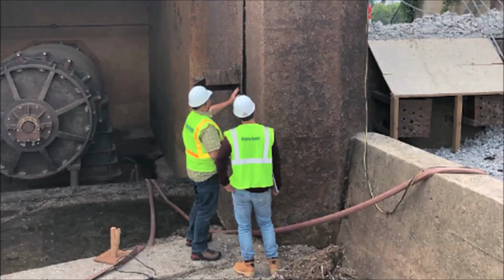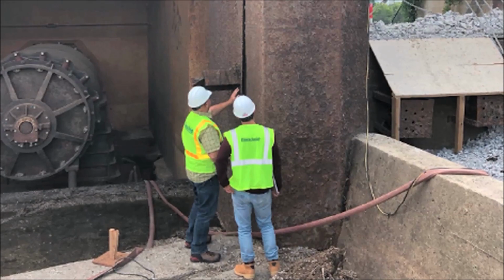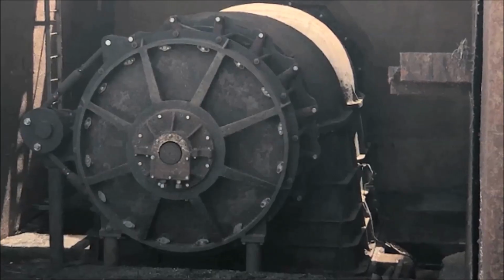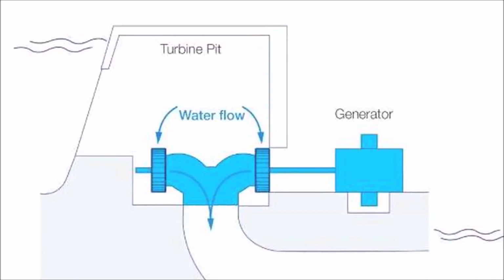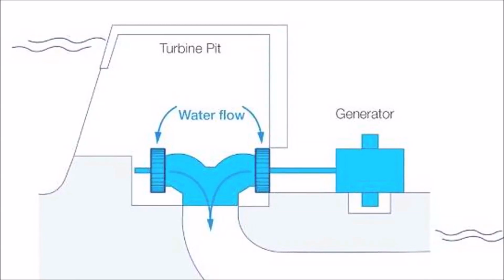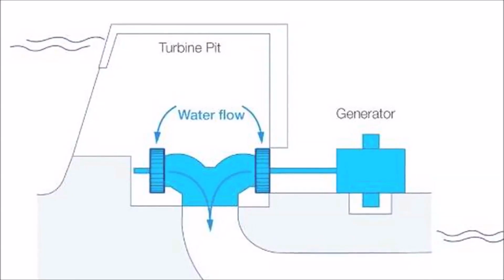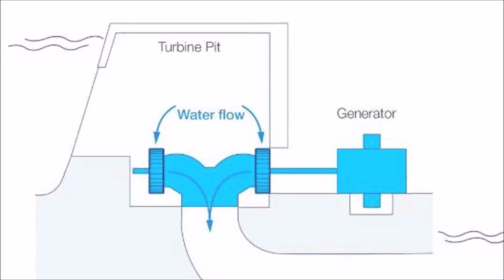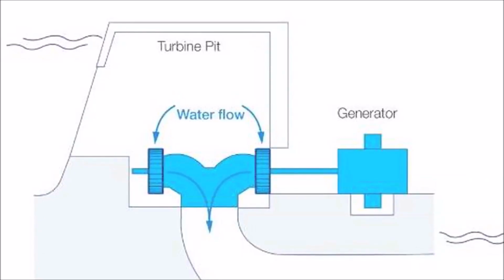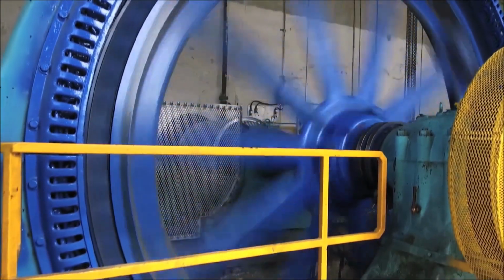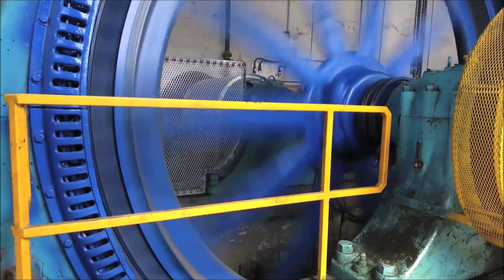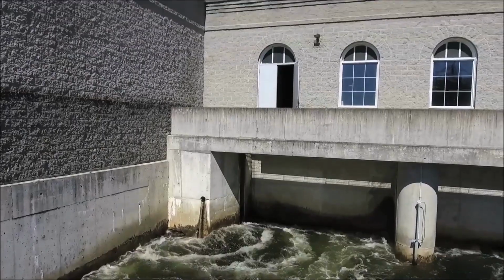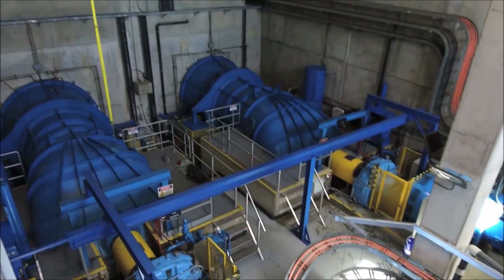The new construction of Plant 2 tripled the capacity from 2 megawatts to a total of 6 megawatts at the Campbellford-Seymour plant. Plant 1 has two Camelback Francis turbines. The Camelback is a unique design where there are two inflows. The first inlet is on the back of the first hump and creates a force opposite to the river flow. The second inlet is on the front of the second hump and balances the force so there is no thrust on the shaft. Plant 2 has two Type S Kaplan turbines manufactured by Alstom.